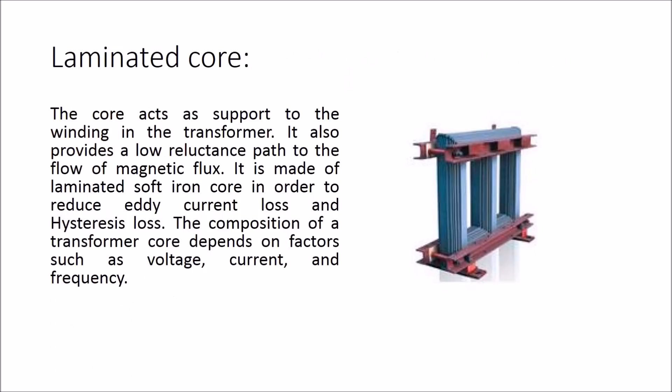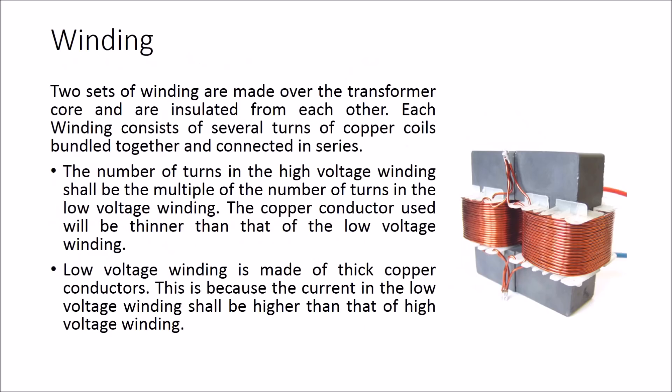The core acts as support to the winding in the transformer. It also provides a low reluctance path to the flow of magnetic flux. It is made of laminated soft iron core in order to reduce eddy current loss and hysteresis loss. The composition of a transformer core depends on factors such as voltage, current, and frequency.